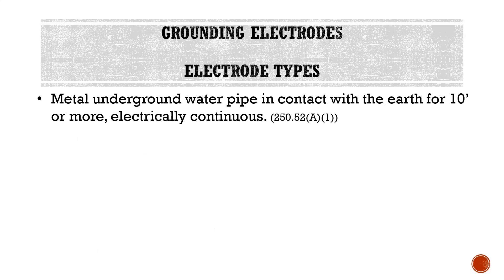Looking at our electrode types individually: A1, our metal underground water pipe — metal underground water pipe in contact with the Earth for 10 feet or more, and it is electrically continuous. So even if we do have metal underground water pipe, it has to be in direct contact with the Earth for at least 10 feet. The whole purpose of a grounding electrode is to make connection to the Earth — that is our goal. We want this electrode to be a really good connection to the Earth.